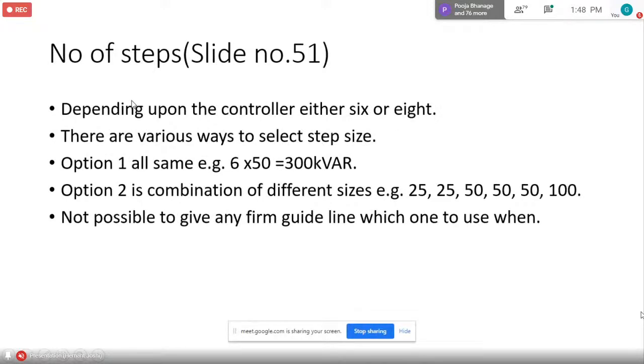Number of steps. Depending upon the controller, either 6 or 8; some manufacturers offer 6, some offer 8. There are various ways to select step size. Option 1, all the same. That is, if you want 6 into 50, that is 300. Option 2, a combination of different sizes: 25, 25, 50, 50, 50, 100. So its total is 300. It is not possible to give any firm guideline on which one to use, so you just see and decide. Usually in most cases the equal one is good enough.